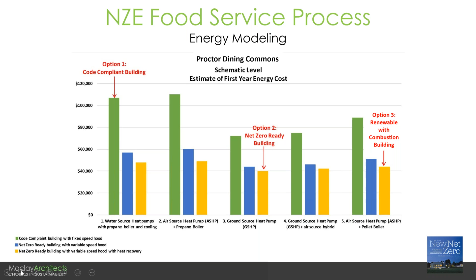In each of these graphs, the green is a fixed speed hood, the blue is a variable speed hood, and the yellow is a variable speed hood with heat recovery. At the time, we were able to get something from Canada that was UL listed, though I'm not sure it's still available. It didn't make a huge increase over just the variable speed. The fixed speed hood means you turn on one burner and it goes to full volume, while with the variable speed, as you turn on more burners, the speed of the hood goes up—that's a pretty good energy-conserving structure. So we ended up with the net zero ready and then the net zero building.